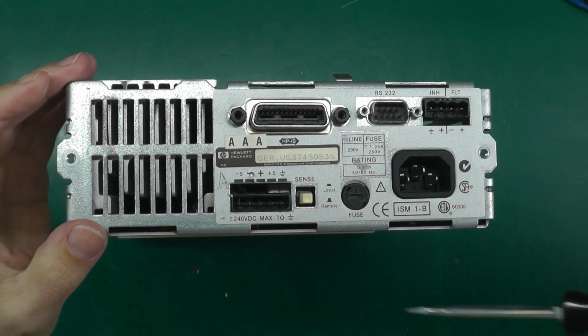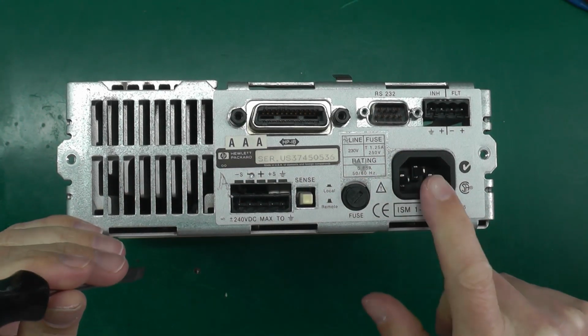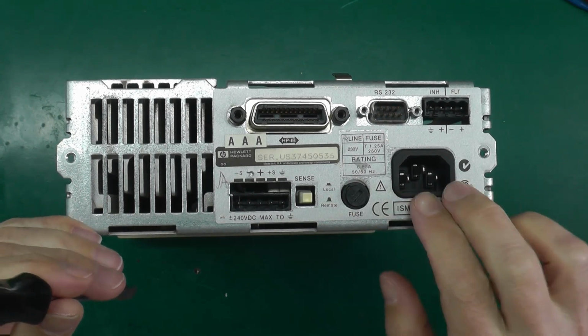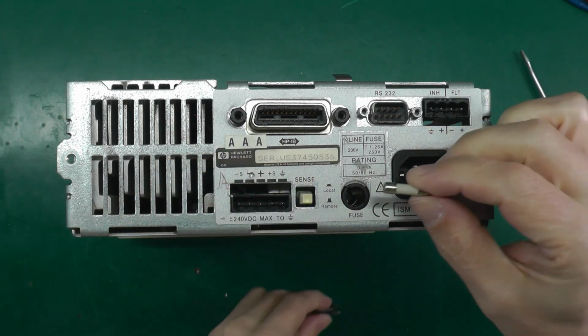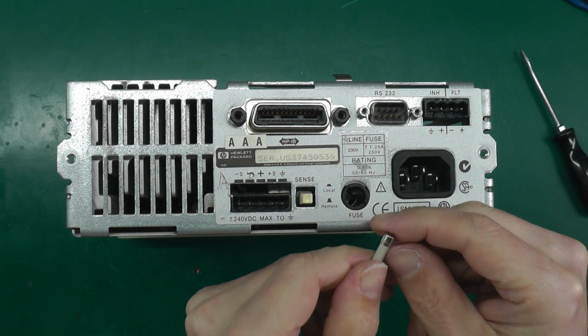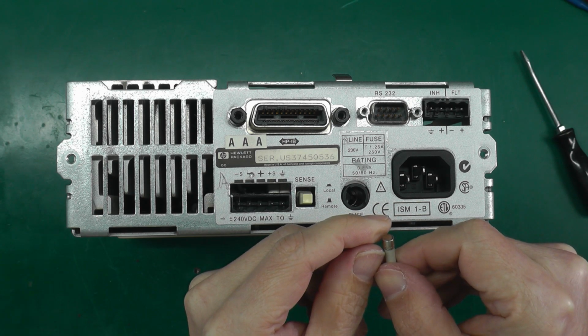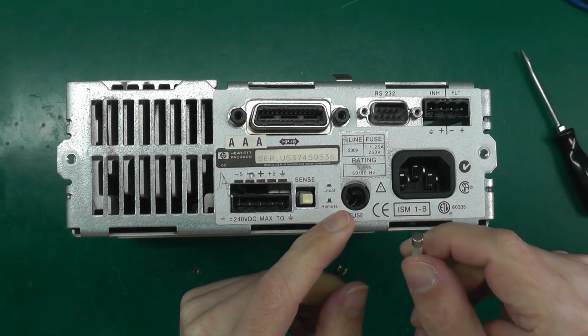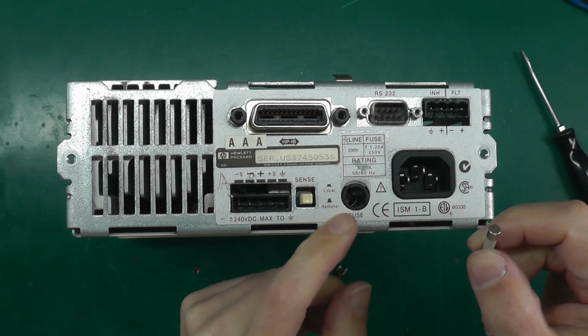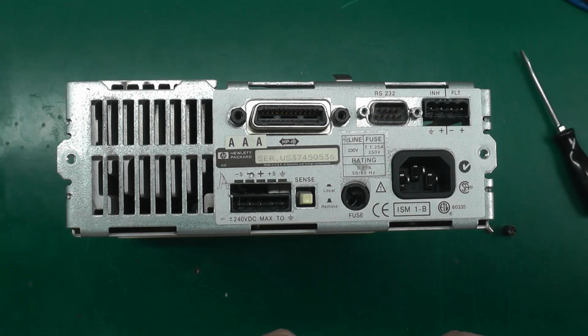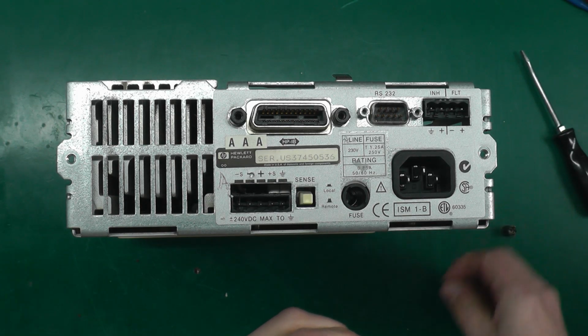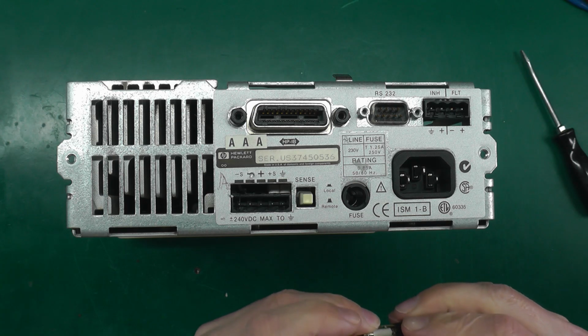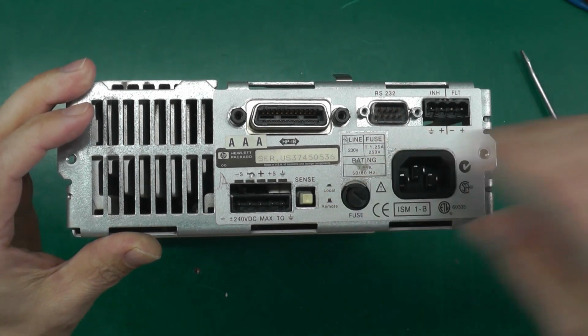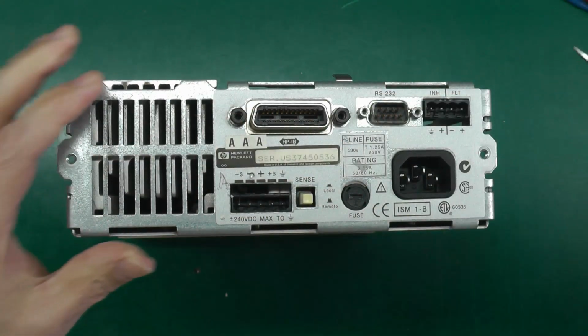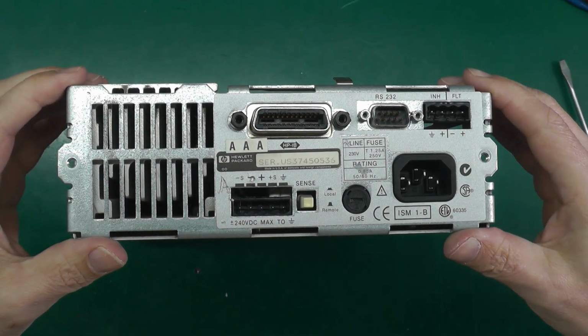So next thing I want to do is check the fuse. I've already gone ahead and checked the resistance across the live and neutral there, and we're getting a good primary winding on the transformer. So we've got a 20mm fuse here, and the size of it is 2.5 amps, so that's definitely the 120 volt option. So I'll have a dig and see if I can find a 1 1/4 amp. Well, I don't have a 1 1/4 amp, so I've got a 2 amp. I guess that'll have to do, so we'll put that in. And there we go. So let's get it ready for a power up.